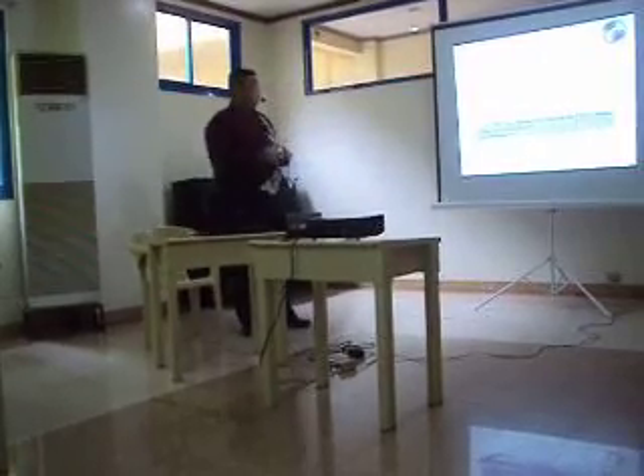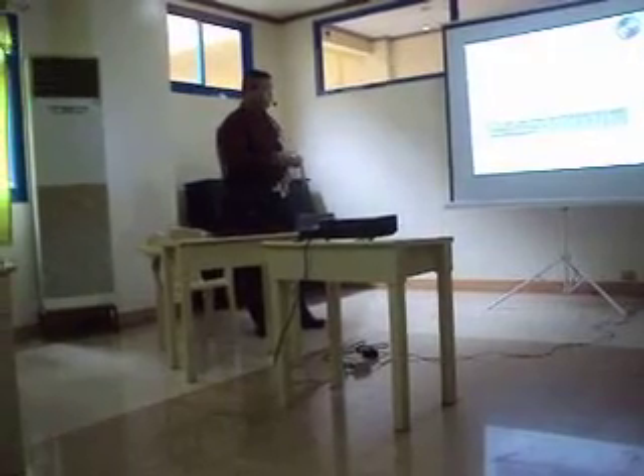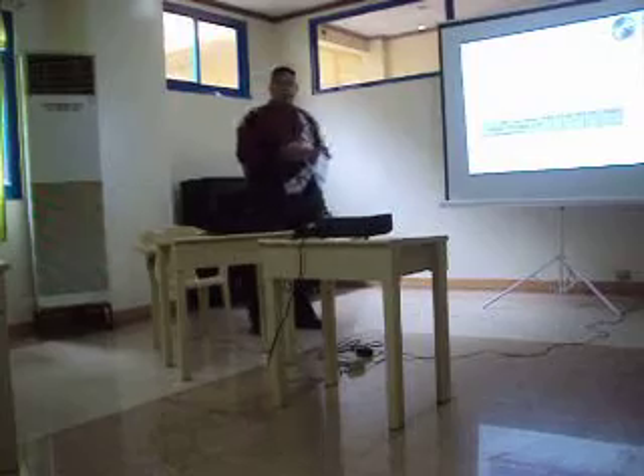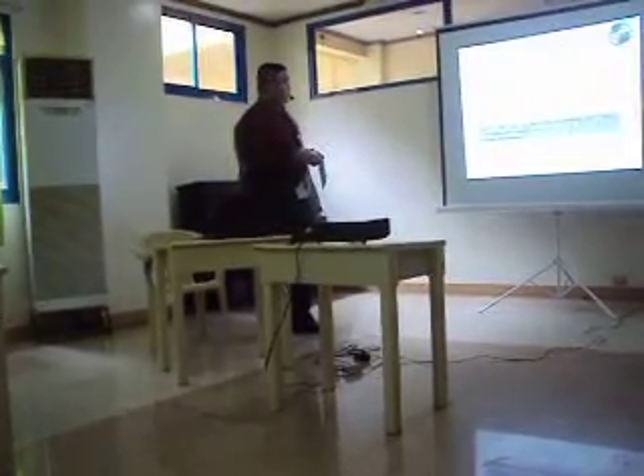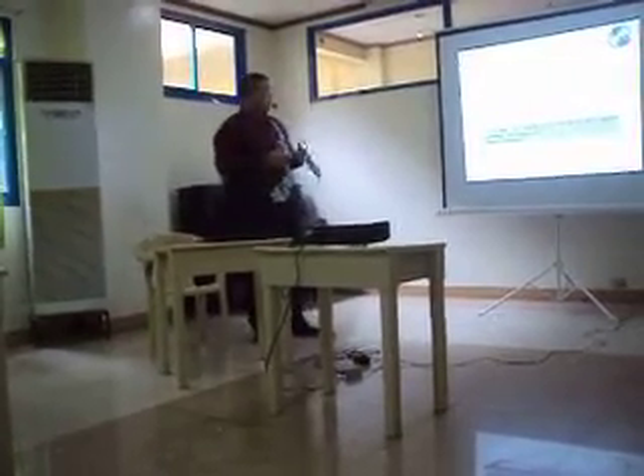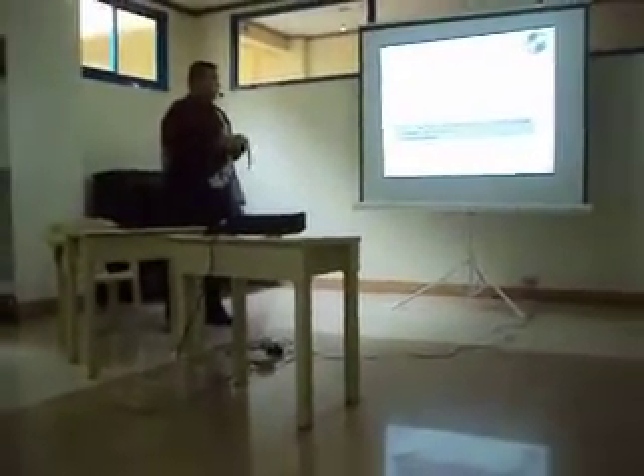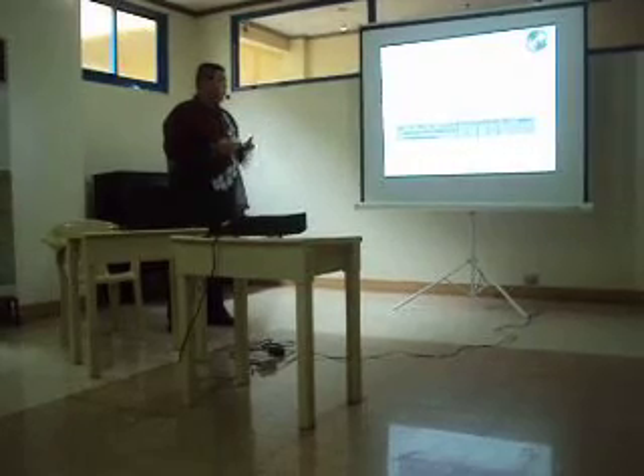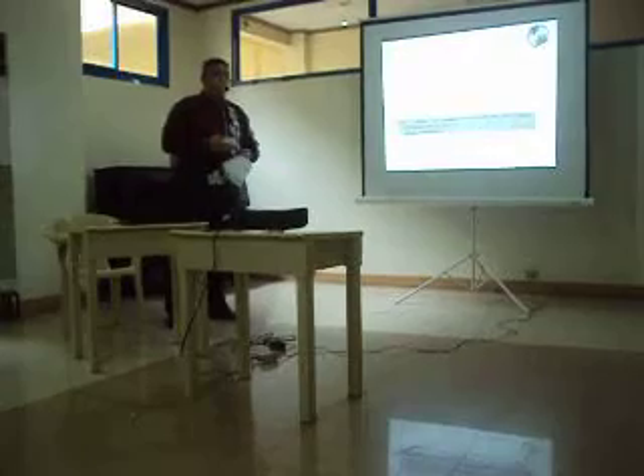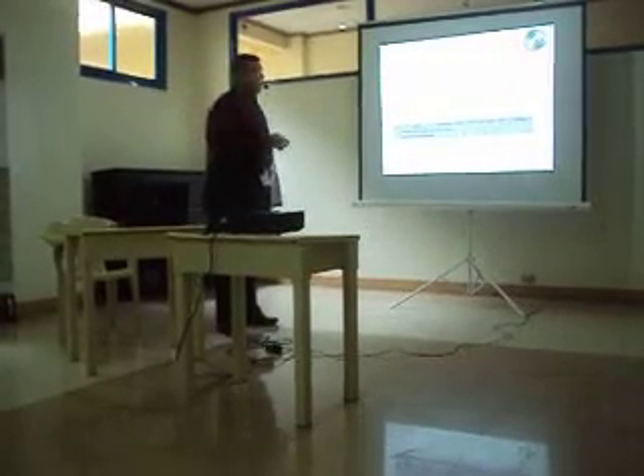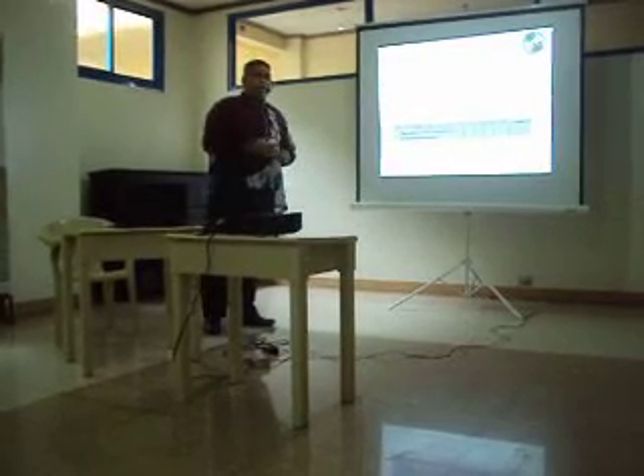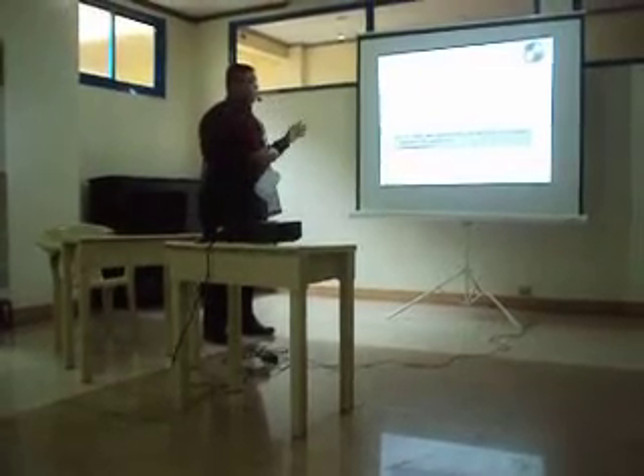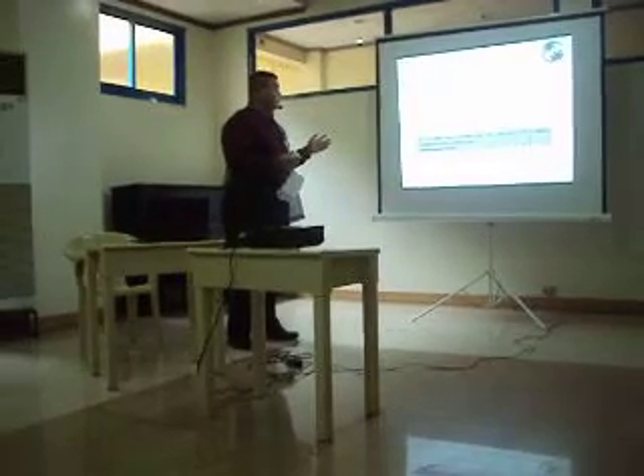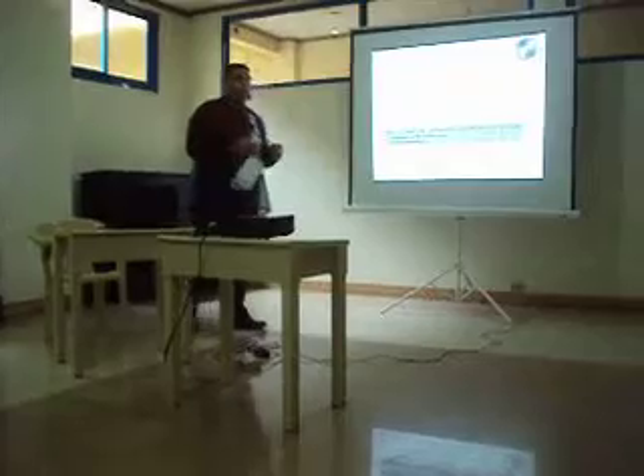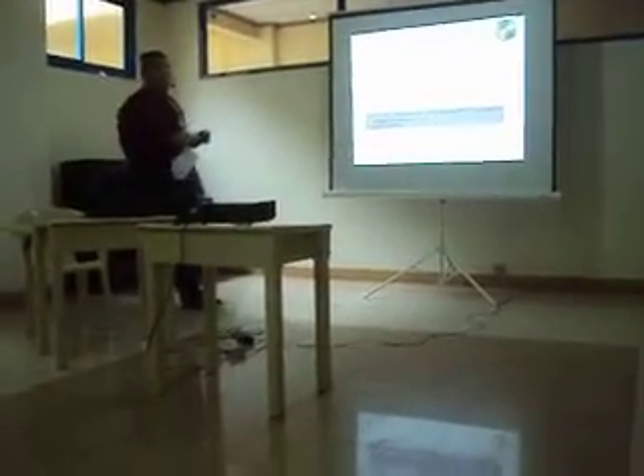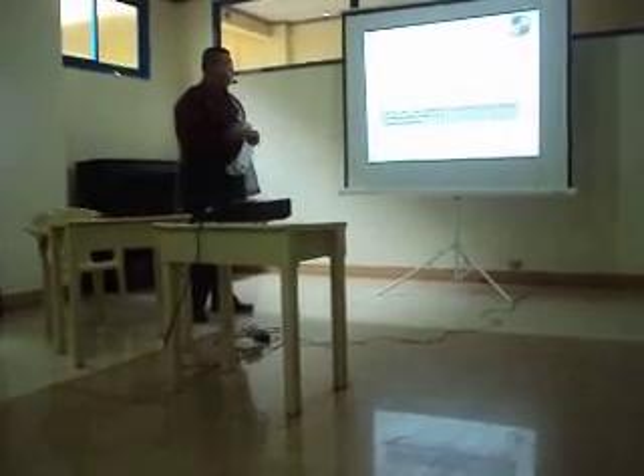Table 2 presents the equipment, which is the X-ray machine. It got an average of 3.83, which is a qualitative description of always. The most significant item in the table is the preventive maintenance of the machine by the hospital administration, which got 3.87. So the equipment used in radiation protection pertains to the X-ray machine. Some protection is given so that the patient will not receive unnecessary radiation. Example, sir, is the collimator.